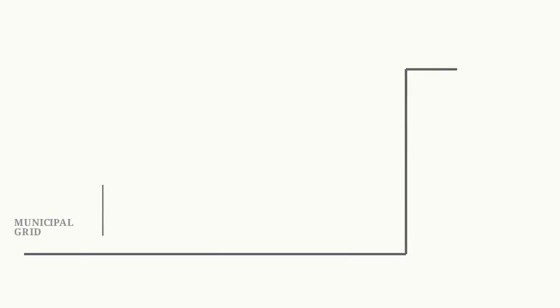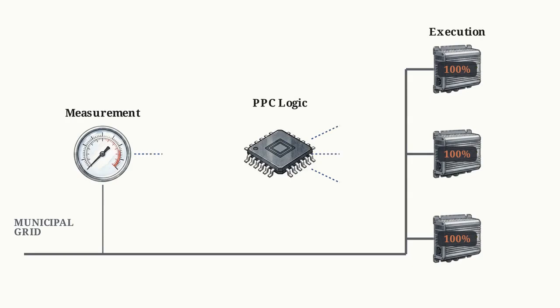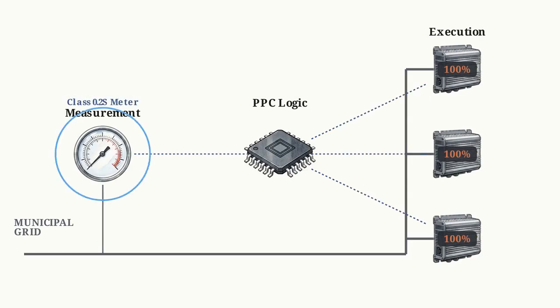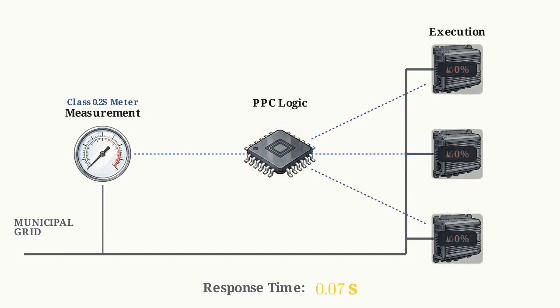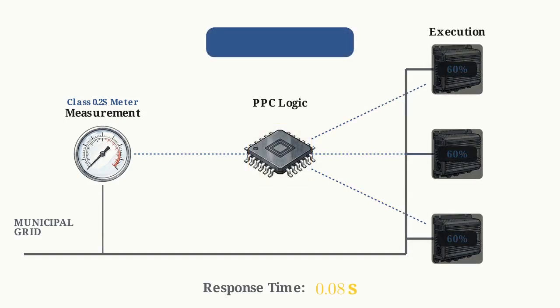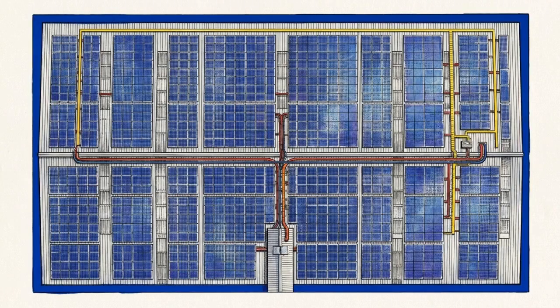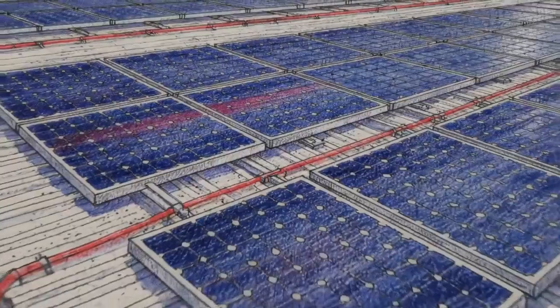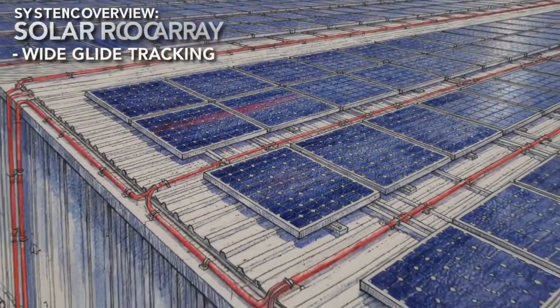We solve this bottleneck by integrating a closed-loop power plant controller. A Class 0.2S meter continuously measures grid exchange. If it detects outgoing power, the controller instantly fires throttling commands to the inverters, curtailing active power output in less than 100 milliseconds. Integrating zero export logic transforms the solar array from a passive power generator into a highly responsive, regulatory-compliant digital asset. Moving upstream from the alternating current inverters, we trace the power back to its source, entering the direct current domain.